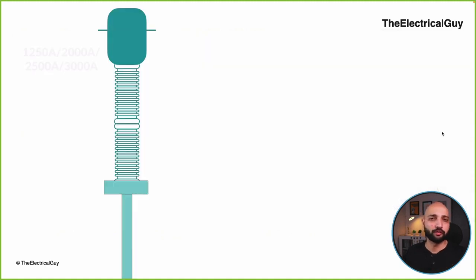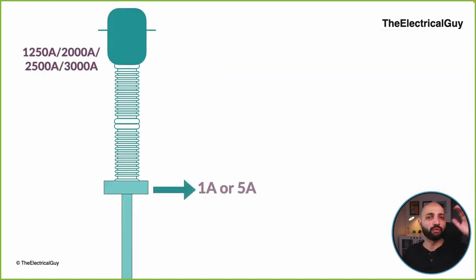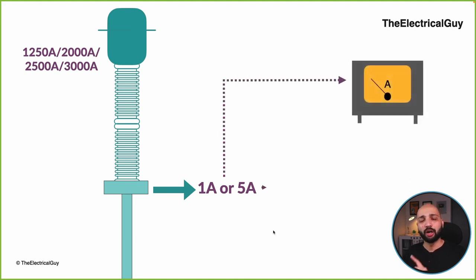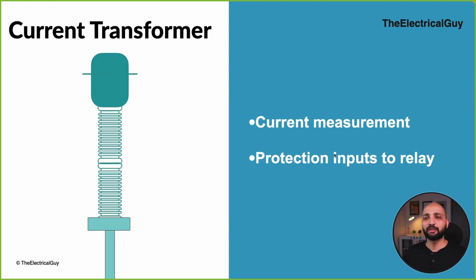So this is the current transformer. Let's say the primary current is 1250 amp, 2000 amp, 2500 or 3000 amp, whatever it is, and then it steps down that current and gives an output of 1 ampere or 5 ampere, which are the preferred values given in the respective IEC standards. And then this output can be given to the meter and to the relay. So the function of the current transformer is current measurement. The input is given to the meters, and it also gives inputs to the relay for protection purposes.